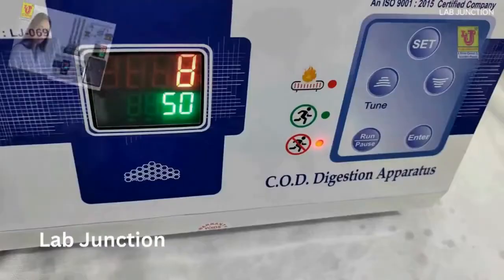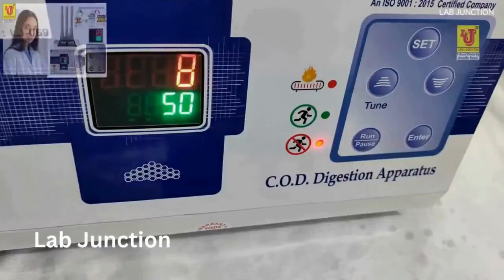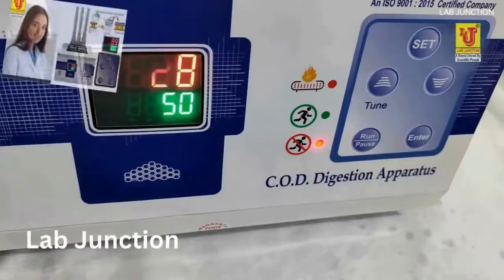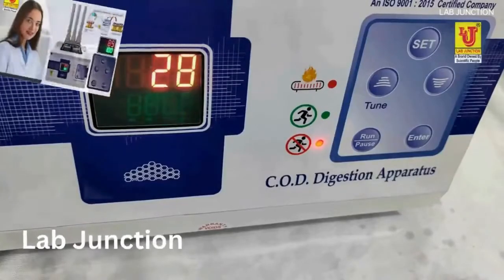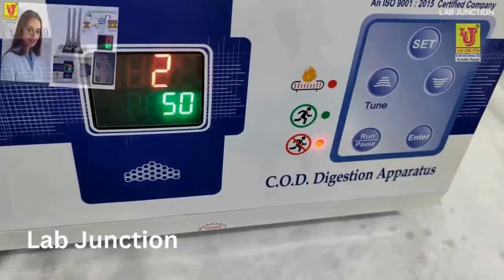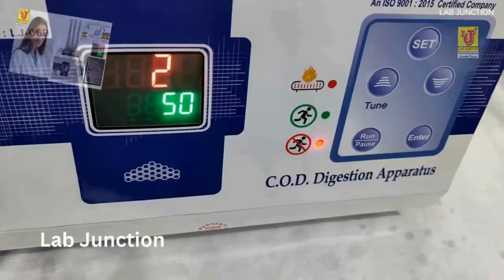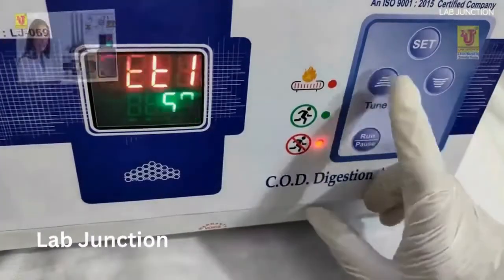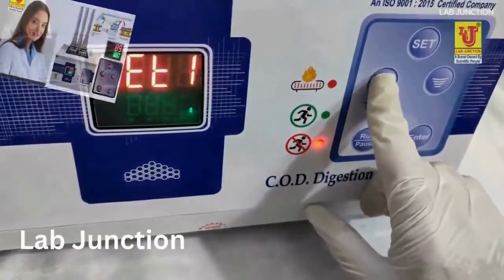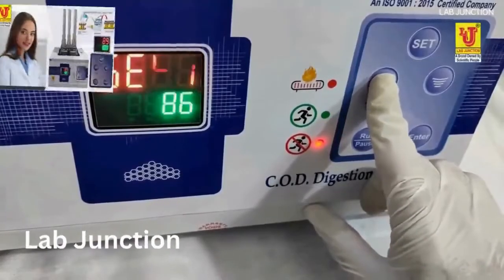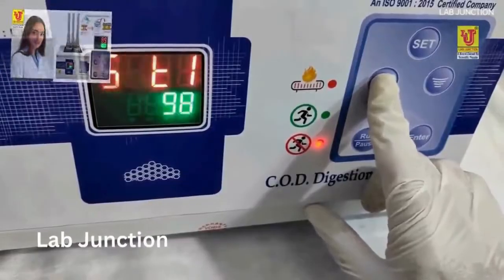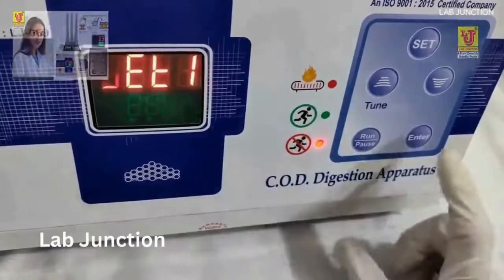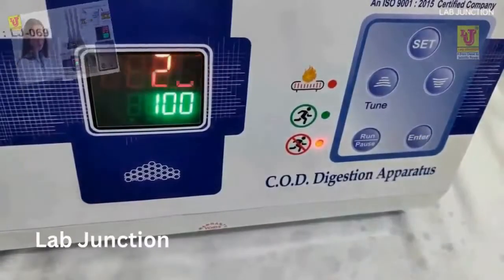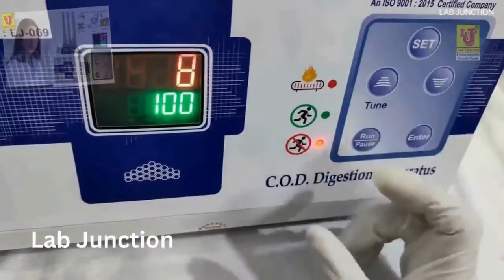Now how to operate this instrument with the help of display keys? First you have to set your temperature. Its maximum range of temperature is 5 degree to 150 degree centigrade. To set temperature, press set key, set one, press up and down keys, you can tune this. Just like I am setting 100. Press enter. These are up and down keys to tune.